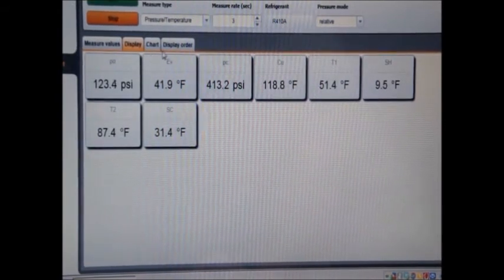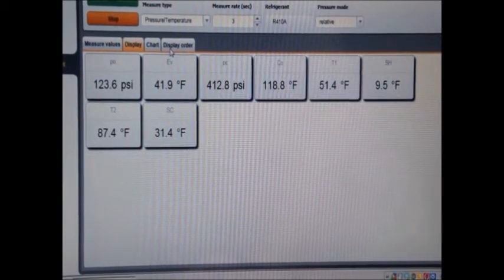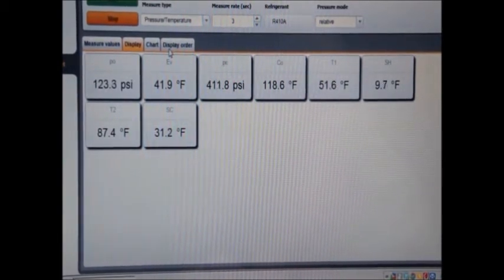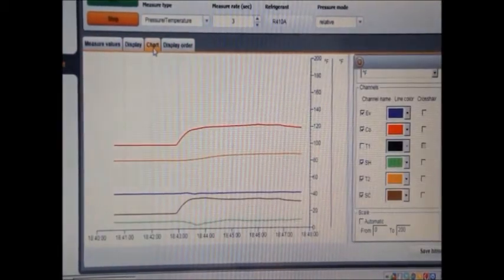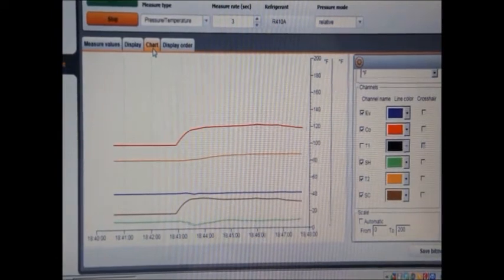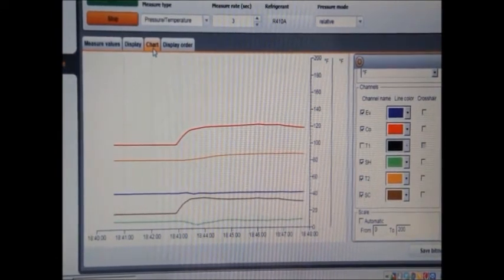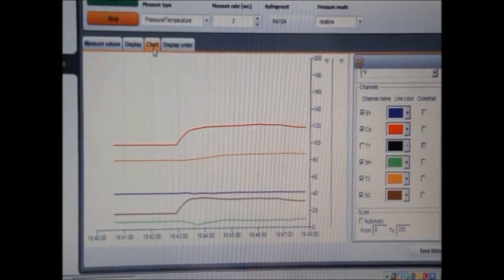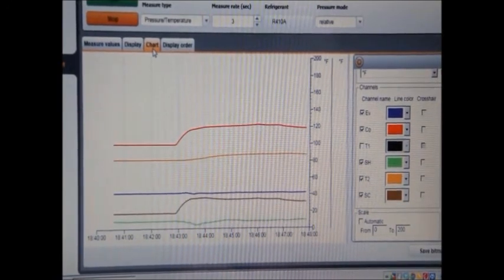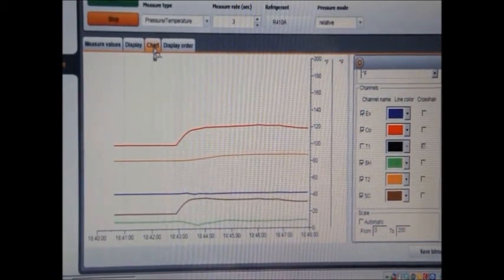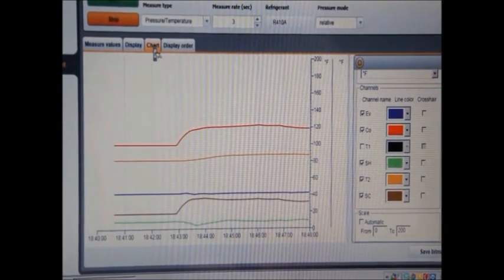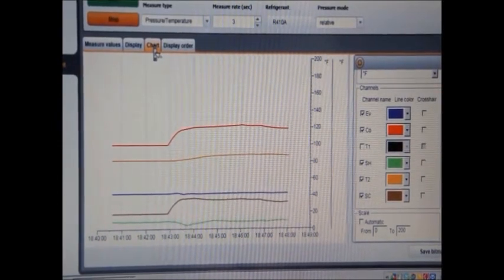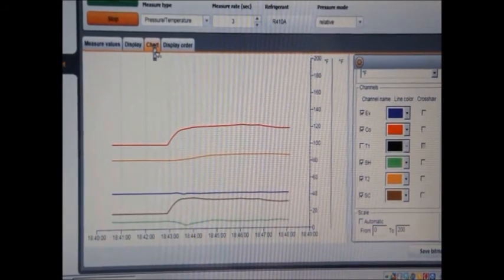Our evaporating temperatures are staying about the same. Our superheat is still staying around 9 degrees. Subcooling though is up at 31.5 degrees of subcooling and it's going down. If you watch it there, you'll see it dropping. I only have it set for every three seconds, dropping slowly. But not all that much. So what we're seeing here is essentially what would appear to be an overcharged unit. In fact, it's just a dirty condenser. If I get that condenser cleaned, get the blockage off of it, what we're going to see is the pressure's going to drop. The liquid can't really get any cooler than it is. It's going to stay about the same temperature and our subcooling will fall right back in line.